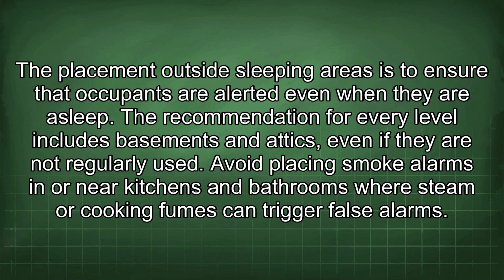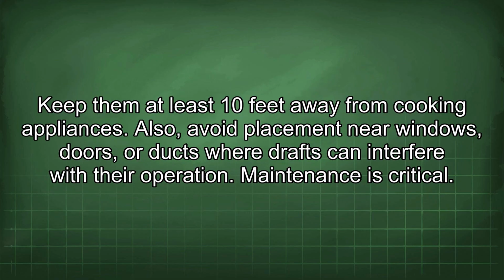Avoid placing smoke alarms in or near kitchens and bathrooms where steam or cooking fumes can trigger false alarms. Keep them at least 10 feet away from cooking appliances. Also, avoid placement near windows, doors, or ducts where drafts can interfere with their operation.